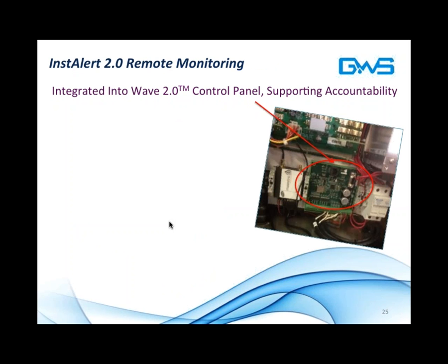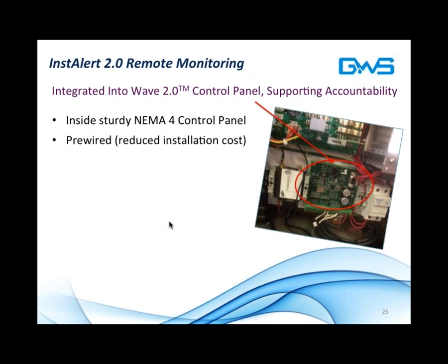InstAlert remote monitoring is integrated into every Wave that we sell. Every Wave control panel automatically comes with it. It supports accountability and transparency of the system operation. It is essentially a wireless communication tool that collects data and transmits that data to ourselves and our service partners. It sits inside a NEMA 4 control panel, water resistant. We can get NEMA 4X as well if required. It's pre-wired to reduce installation costs, as is the entire system. And it measures or monitors three key parameters.